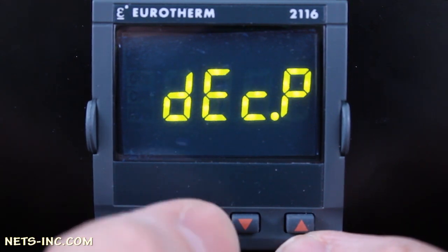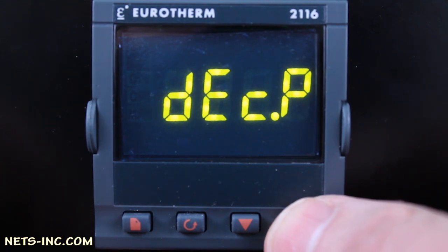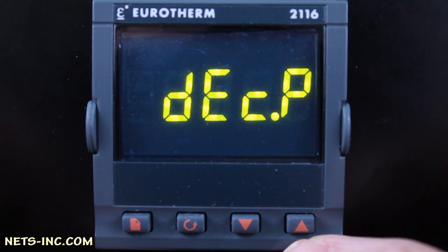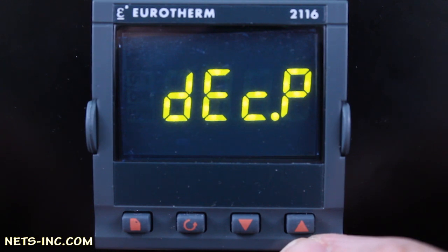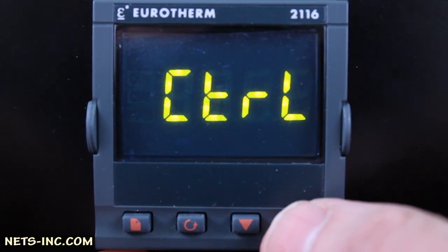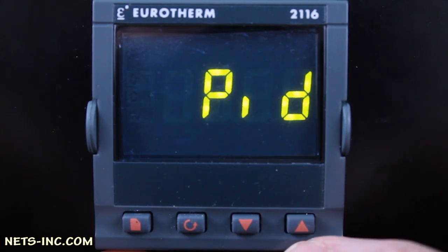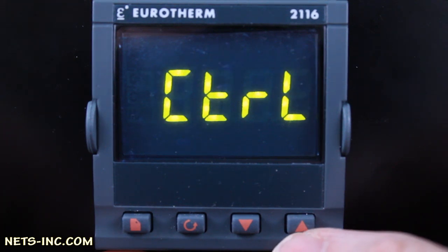Press the Up Arrow and for our application we are not going to have any decimal points. Should you want a decimal point, continue pressing the Up Arrow and you will notice the decimal point marches across the screen. Press Scroll one more time to display CTRL — this is the control mode. We want our instrument to be a PID controller. Press the Up Arrow and it is set for PID control.